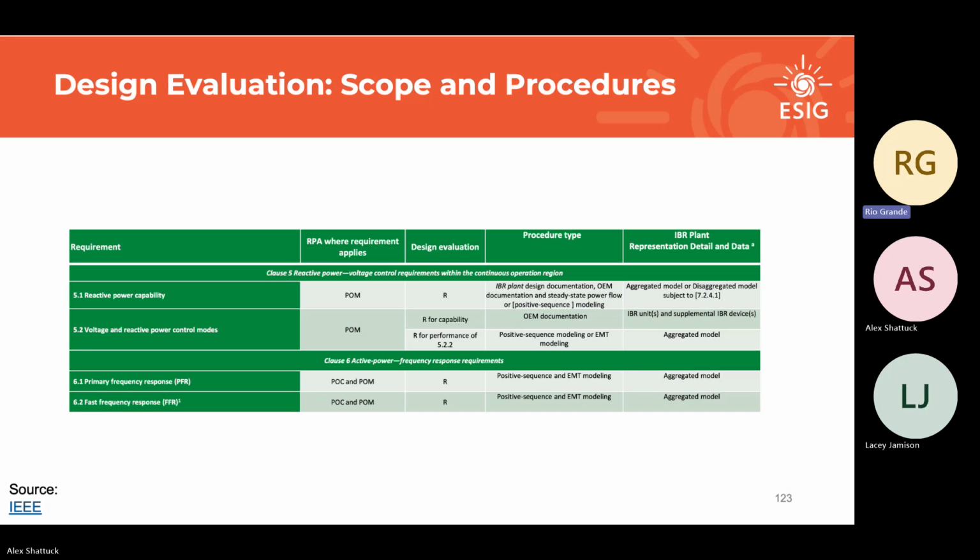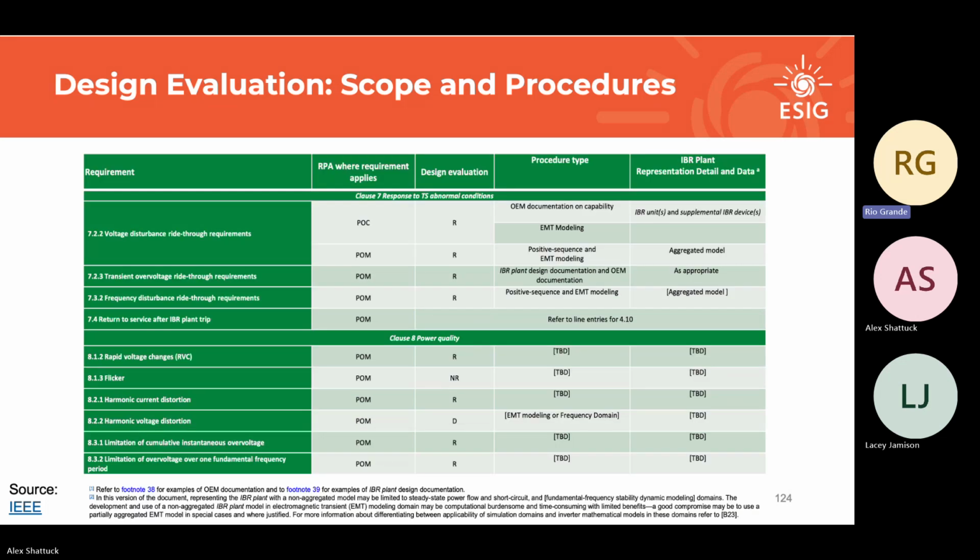But the thing to keep in mind is there is a requirement in the design evaluation to show that your plant is doing PFR and FFR right. And again, it won't catch everything, but it's a good check, right? If FFR, AVR is wrong, I'm looking into everything now.